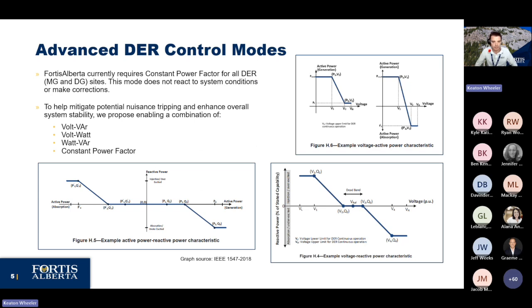This leads us into advanced DER control modes. Right now, FortisAlberta requires constant power factor for all DERs, both MG and DG sites. This mode doesn't react to system conditions or really make corrections, so when voltages move, these DERs don't react to try and correct that. To help mitigate nuisance tripping issues and enhance overall system stability, we're moving to advanced DER control, a combination of Volt-Var, Volt-Watt, Watt-Var, and constant power factor. These are the modes we'll be employing going forward, including for some of the older generators already in our network.